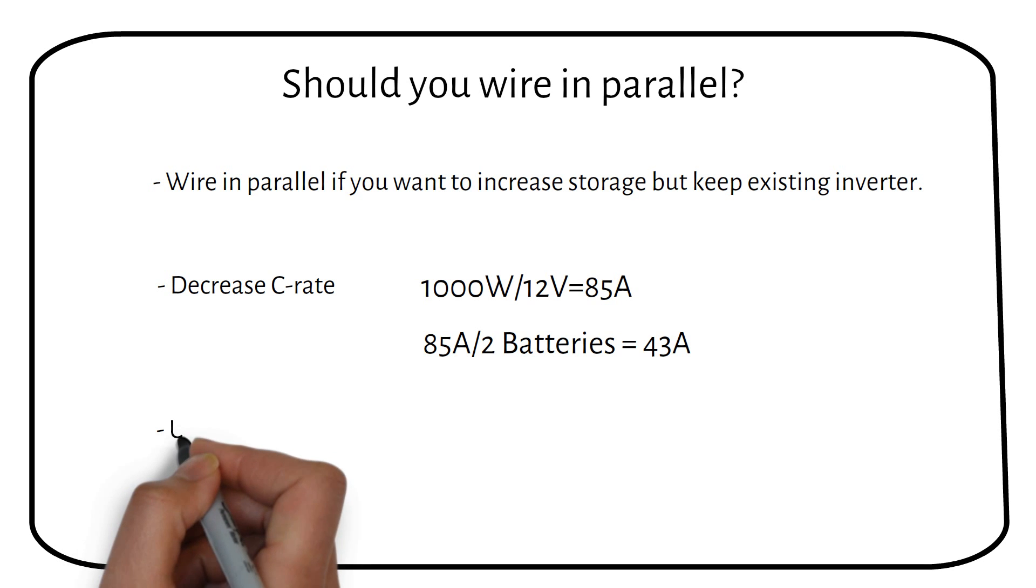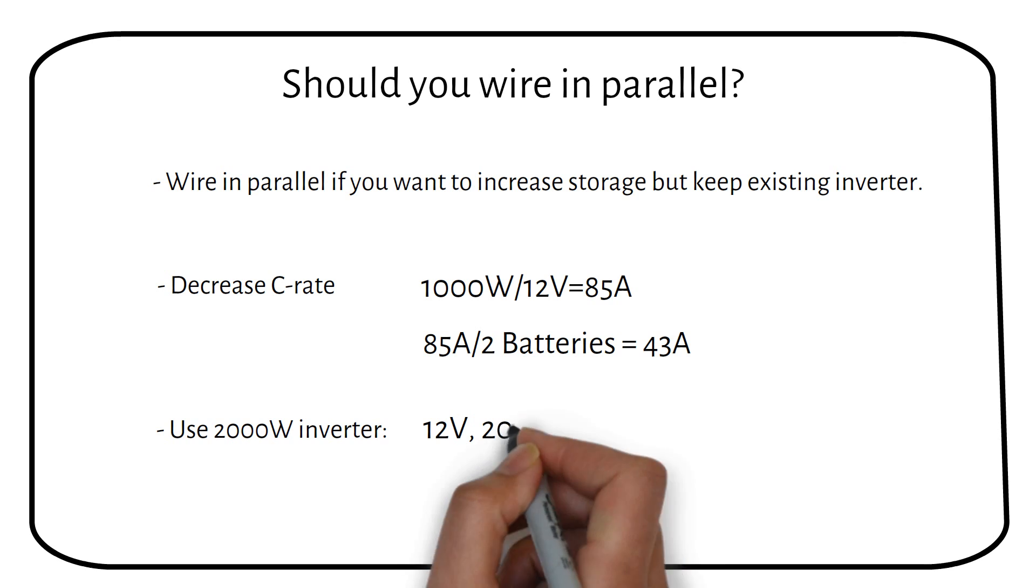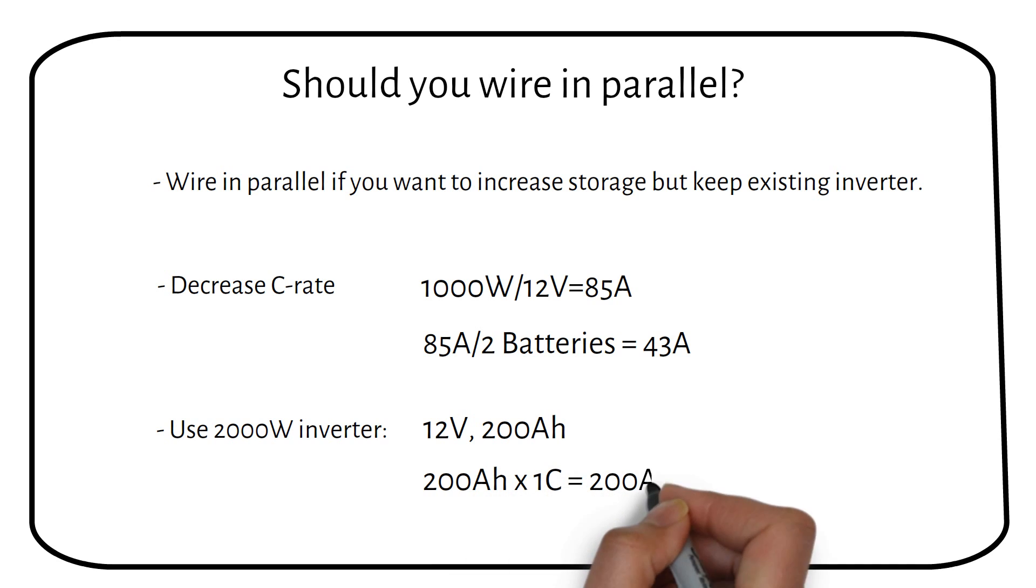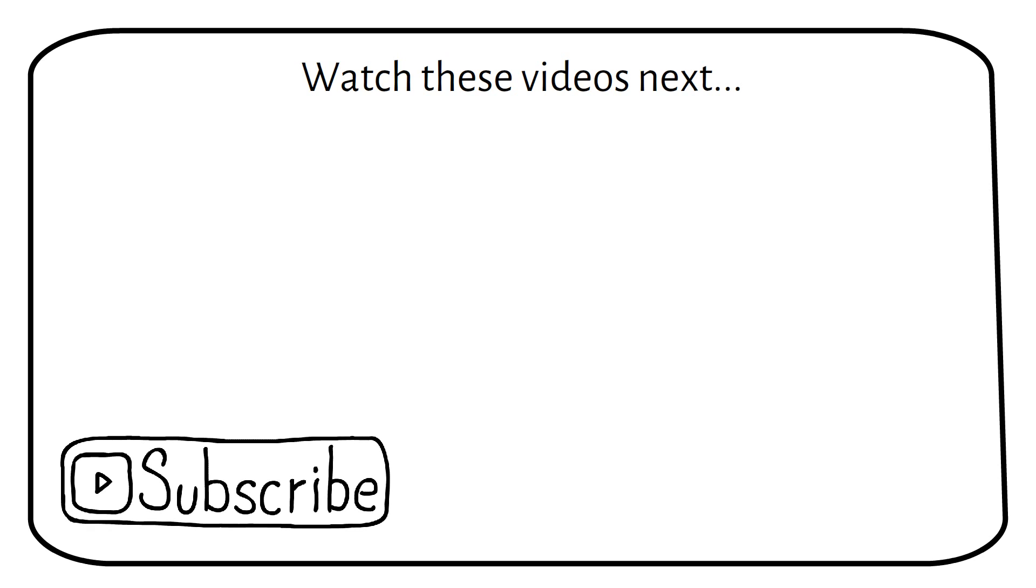To power a 2000W inverter on a 12V system with lithium batteries, you need at least two 12V 100Ah batteries in parallel. This becomes one big 12V 200Ah battery. Such a battery has a C-rate of 1C. Thus, you can draw a maximum of 200A, while the inverter will draw a maximum of 167A. This battery is correctly sized. Let me know your questions in the comments. Subscribe for more videos like this, and watch these videos next.